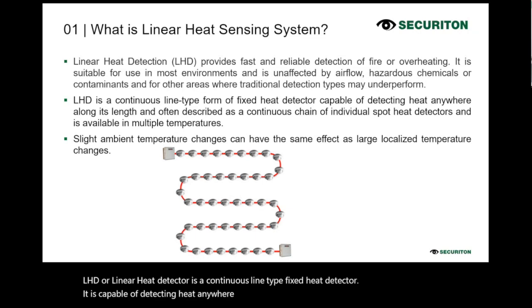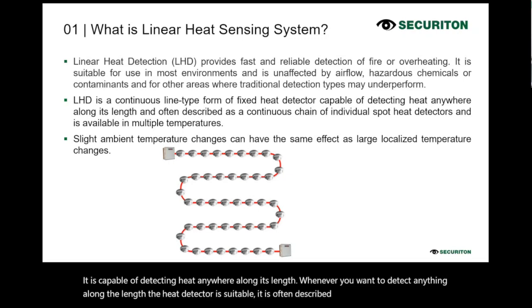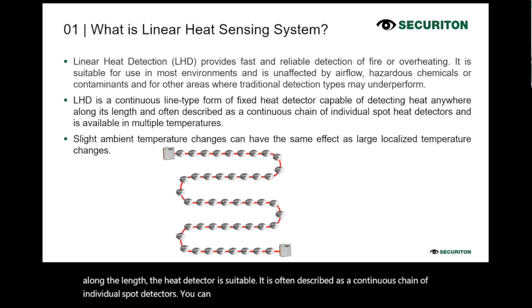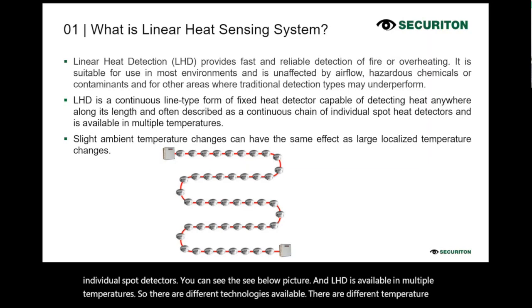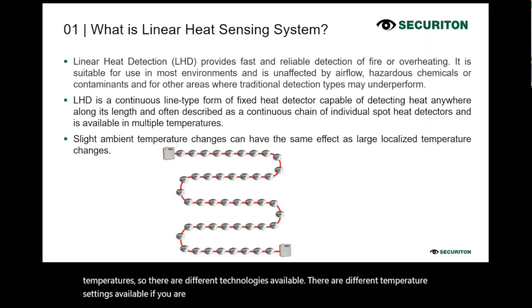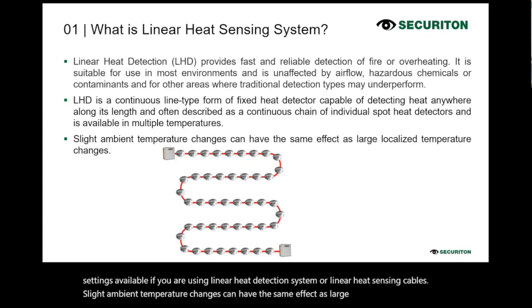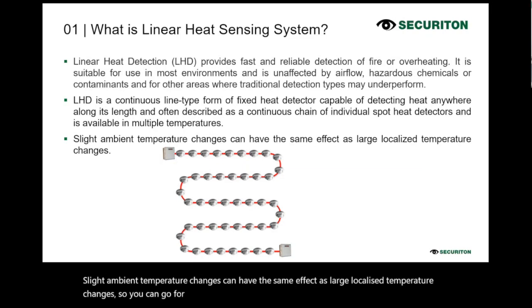Whenever you want to detect anything along the length, the heat detector is suitable. It is often described as a continuous chain of individual spot detectors. You can see the picture below. And LHD is available in multiple temperatures. There are different technologies and different temperature settings available if you are using a linear heat detection system or linear heat sensing cables. Slight ambient temperature changes can have the same effect as large localized temperature changes. So you can go for a vast range of applications here.